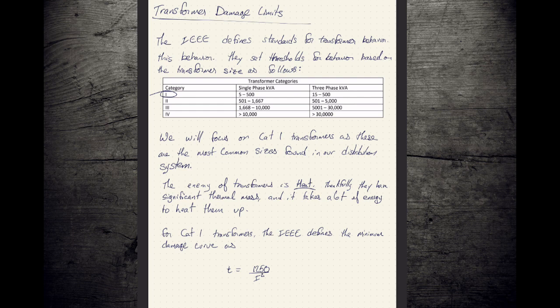And so the standards that these transformers have to be built to, they have to account for both of those things. They have to account for heating, like did we flow so much energy through this that the tiny little connectors where our lugs are attached melted off? But also, is the bracing internally robust enough? Is it tough enough that when this fault current puts the squeeze on it, it's not going to twist itself into a pretzel and not work anymore?